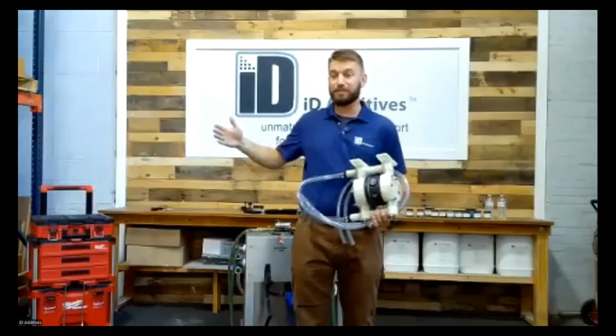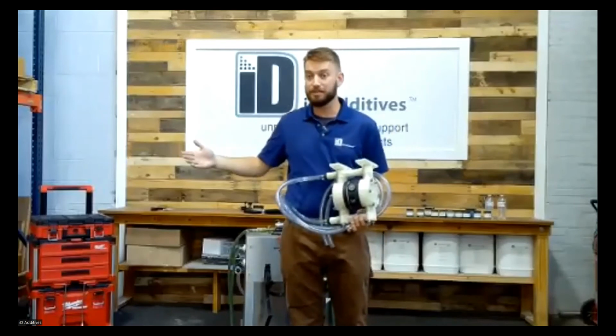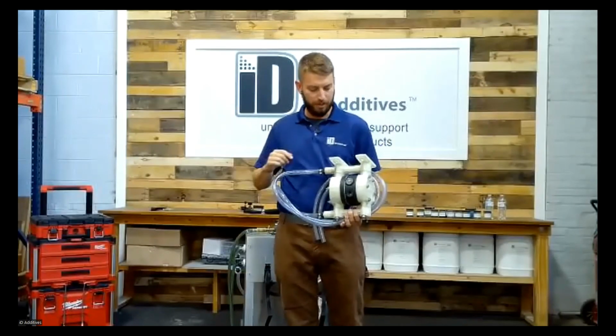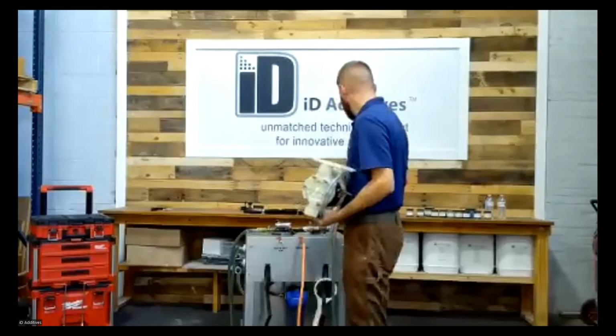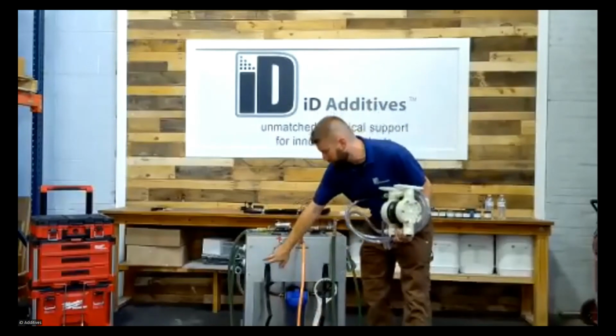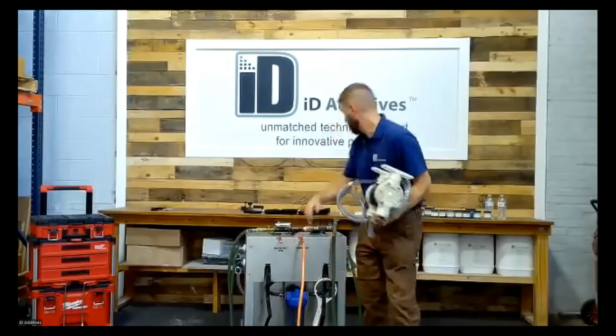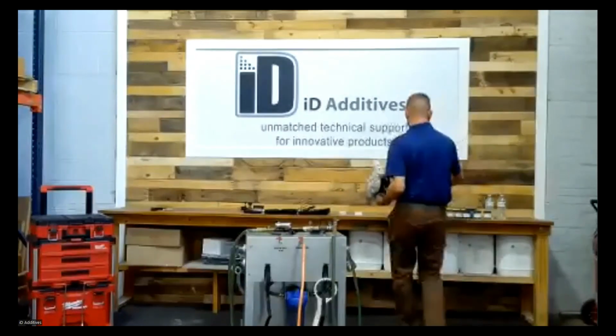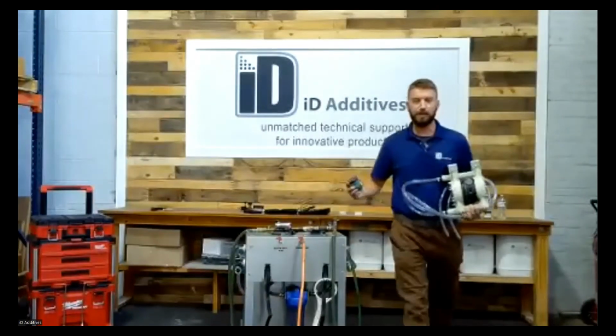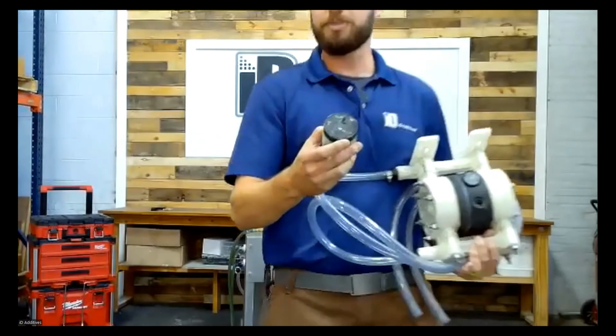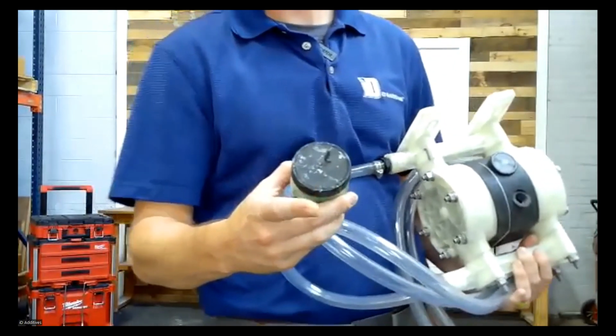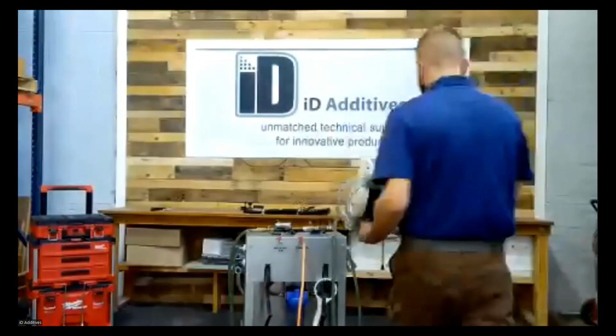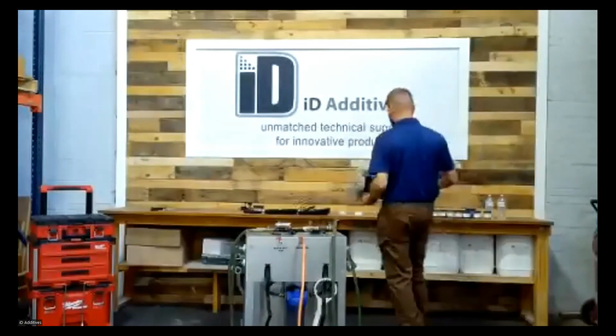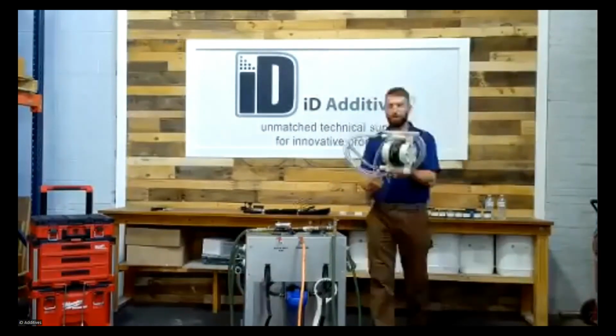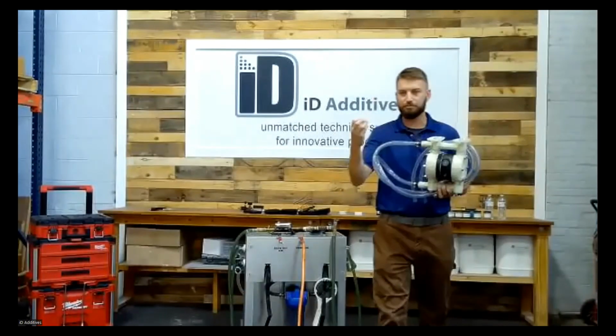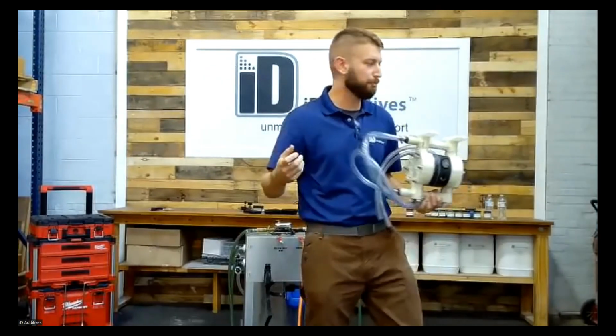What can happen, as that gentleman mentioned, especially if the unit will be down for 1 to 2 weeks, or if you leave it sitting for 6 months without backflushing with water, is some of this chalk-white residue builds up. Here's a good example of chemical left on and not dried -- it turns this chalk-white coloration. That same chalkiness can build up in the balls of these manifolds and cause them to stick. They're PTFE balls.